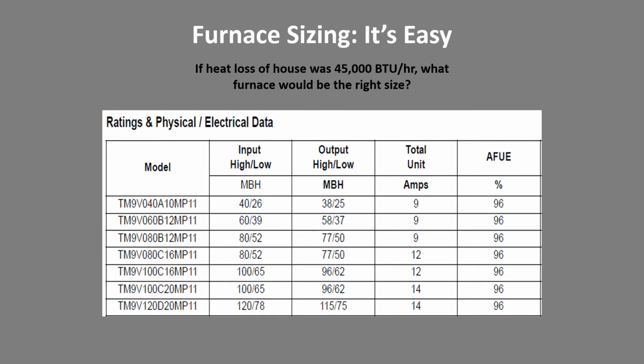It's really simple. You just get the capacity tables out. This one here is for a two-stage piece of equipment. It tells you the input at 40K on high, 26K on low. The output, this is obviously a high efficiency furnace, is 38 and 25. And again, we size on the output of furnaces, not the input.